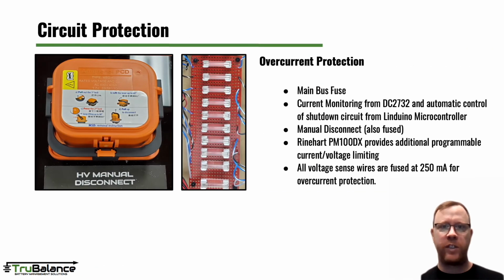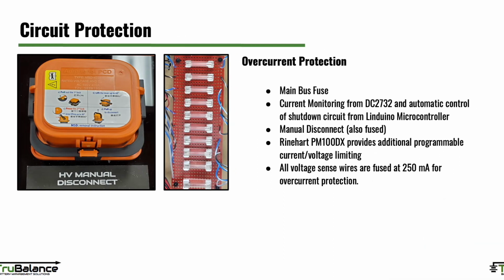Our system is designed with several overcurrent protection devices. The isolation relays are automatically opened if the current sensed by the 2732 is measured above a user-defined maximum operating value. Additionally, we have included 2 fuses in the high voltage circuit. One fuse is located on the positive bus, and the second fuse is built into the high voltage manual disconnect, which also serves as our service plug.